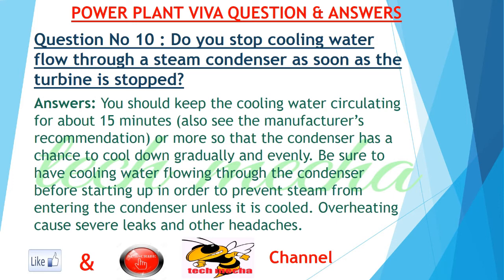Question number 10: Do you stop cooling water flow through a steam condenser as soon as the turbine is stopped? Answer: You should keep the cooling water circulating for about 15 minutes — also see the manufacturer's recommendation — so that the condenser has a chance to cool down gradually and evenly. Be sure to have cooling water flowing through the condenser before starting up, in order to prevent steam from entering the condenser unless it is cooled. Overheating causes severe leaks and other headaches.